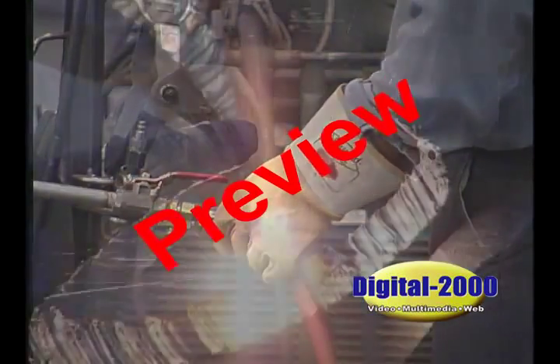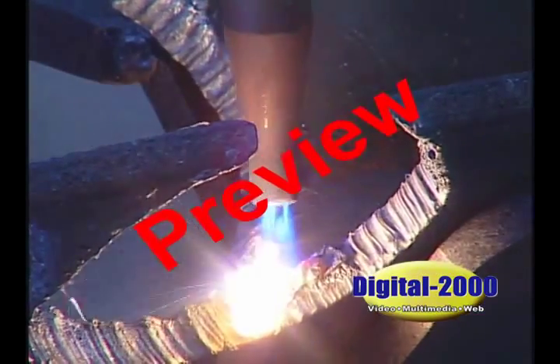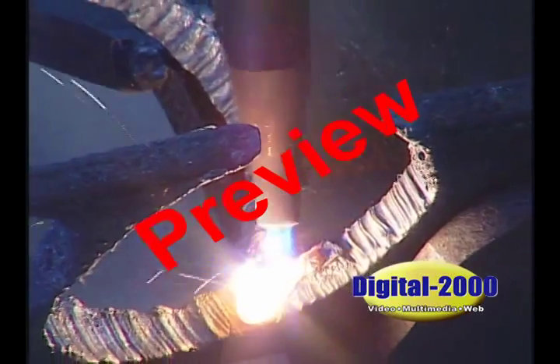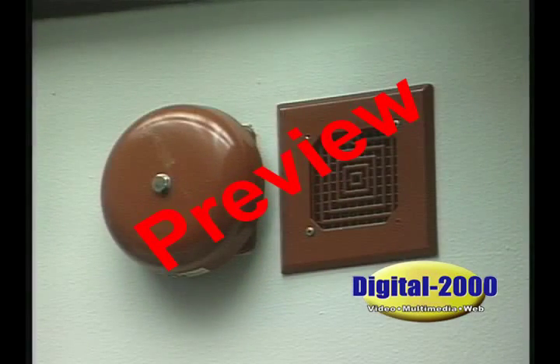Performing hot work in a confined space requires unusual precautions and must be completed with the utmost of responsibility. Persons performing hot work must check for smoke detectors in the area that they will be working. This is necessary to avoid unwanted alarm activations. Be sure the smoke detectors are returned to normal operating conditions when the hot work is completed.